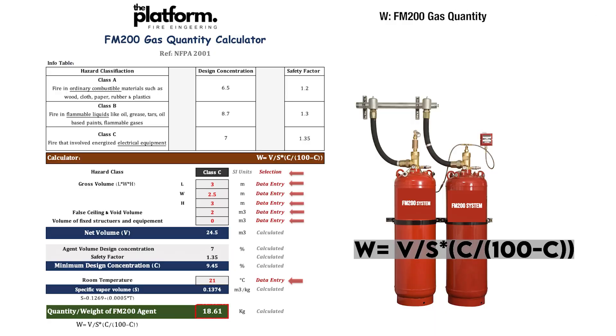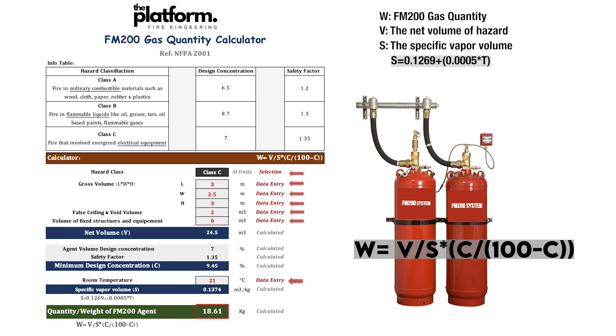W is the FM 200 gas quantity in kilograms. V is the net volume of the hazard structure, calculated considering the gross volume of the room minus the volume of fixed structures. S is the specific vapor volume, which we can get by applying an equation using the room temperature. C is the minimum design concentration, selected based on the hazard classification and multiplied by a safety factor.